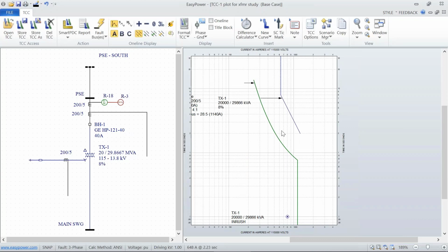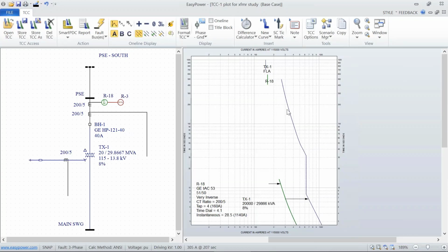And this has to do with the knee and the curve. Now, one thing we haven't touched on, and that is usually you see two curves. One's the 100% damage, and the other's the 58% damage curve. And that's due, in this case, to the fact that we have a non-solidly grounded transformer. And so with some resistance in this neutral leg, the effect of having a single line to ground fault will be generating currents much less than the range we're talking about for fault currents here.